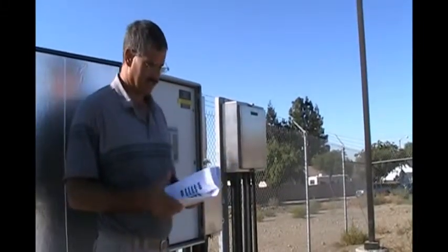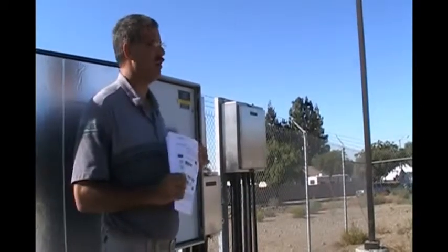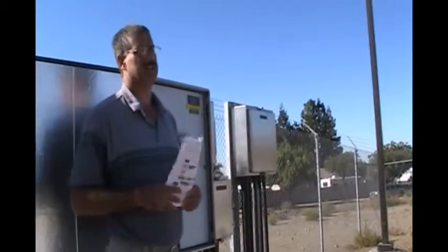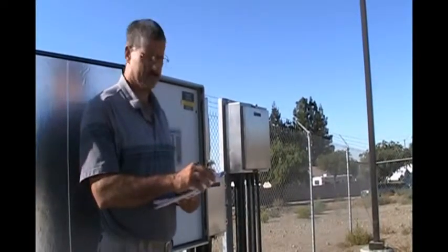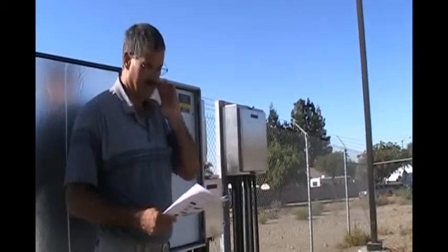So you can operate it in a percent mode operation only. Okay? This does not tie into any flow. The flow will be predicted by the pressure in the line. So whatever the pressure is based on that percent valve open, that's the flow you'll get. So this is really not something we want to do on any kind of a regular basis. It's just strictly a maintenance option if you have the need to do so.